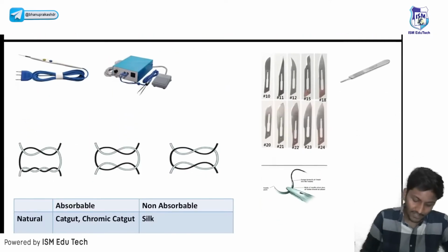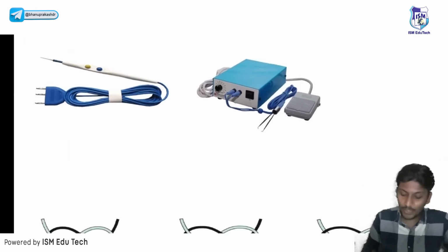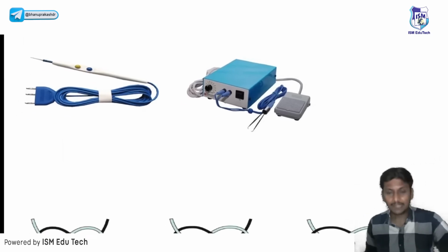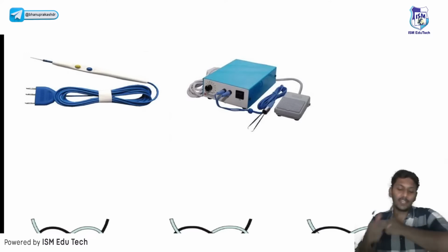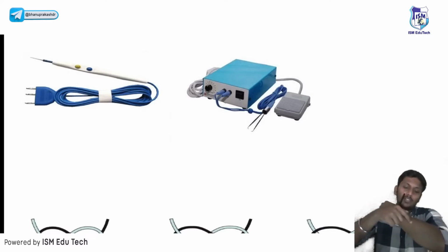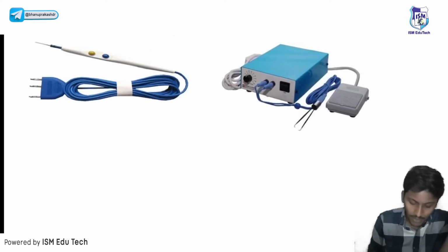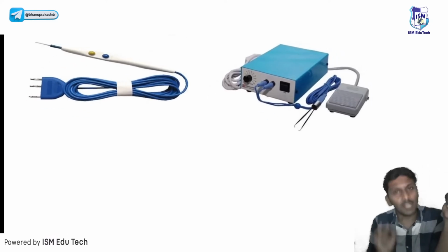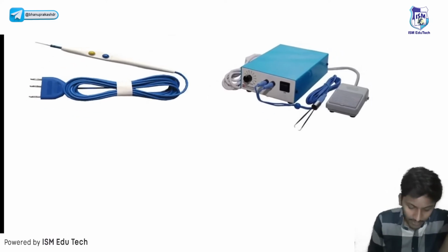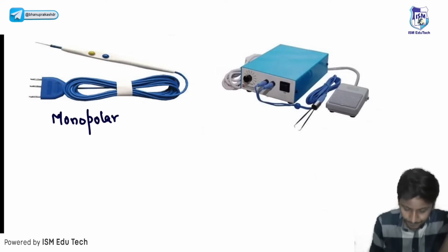Cauteries are indispensable surgical instruments utilized for incisions and minimizing bleeding during procedures. They possess the ability to both cut and coagulate tissue efficiently, thus enhancing surgical safety. There are 2 primary types of cauteries, monopolar and bipolar. Monopolar cautery requires a grounding pad and poses certain risks for patients with pacemakers, while bipolar cautery does not.